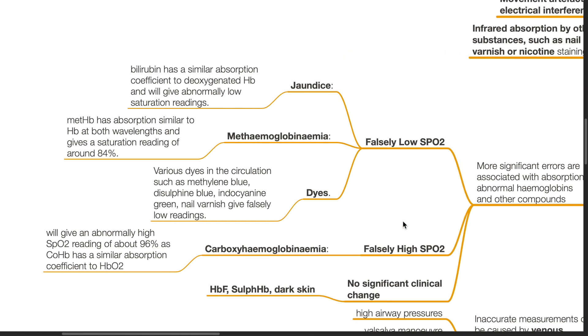Falsely low SpO2 can result in the presence of jaundice. Bilirubin has a similar absorption coefficient to deoxygenated hemoglobin and this will give an abnormally low saturation reading. In the presence of methemoglobin with absorption spectra similar to deoxygenated hemoglobin at both wavelengths, this gives a saturation reading of around 84%. In the presence of dyes such as methylene blue, disulfine blue, indocyanin green and nail varnish, falsely low readings will occur.